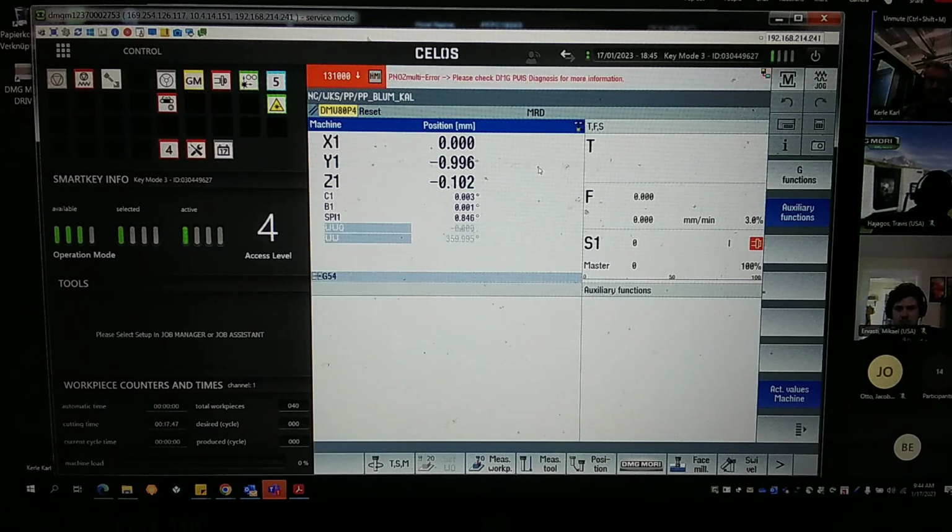And what it means is that sometimes, if the CELOS software itself gets crazy, nothing works, everything looks frozen on the screen, we cannot know what the reason is. Is it the CELOS data management, or is it the HMI operate software responsible for the gray screen? Only after they introduced these LEDs, if this LED is changing to red, then we know the reason is that internally the CELOS data management is crashing.